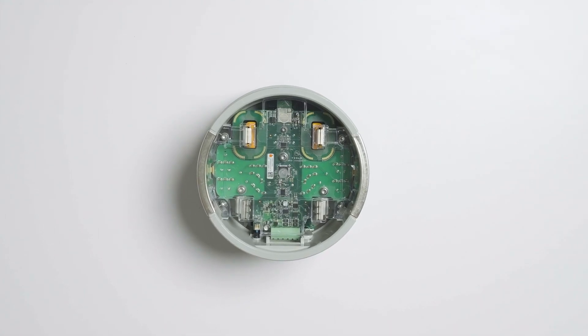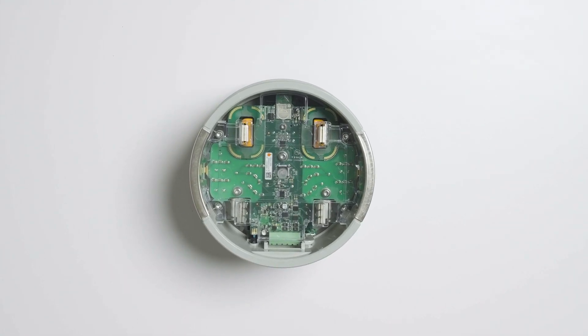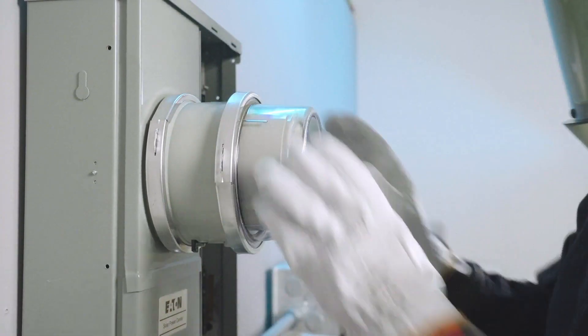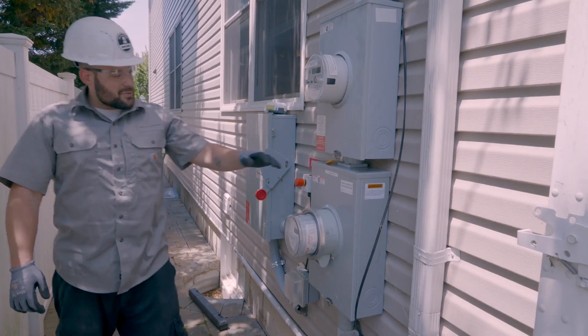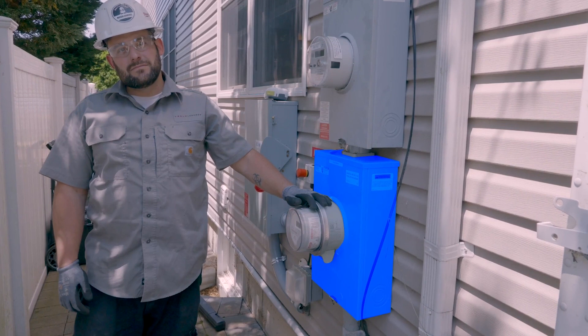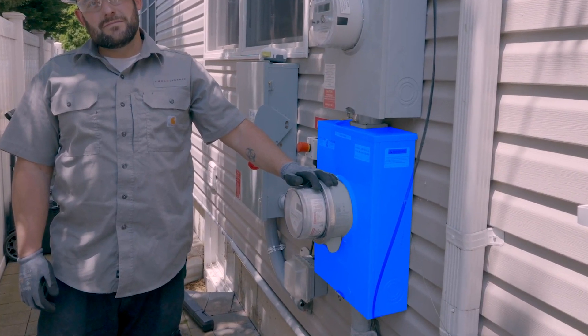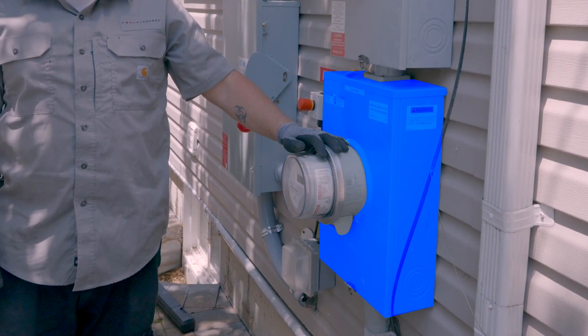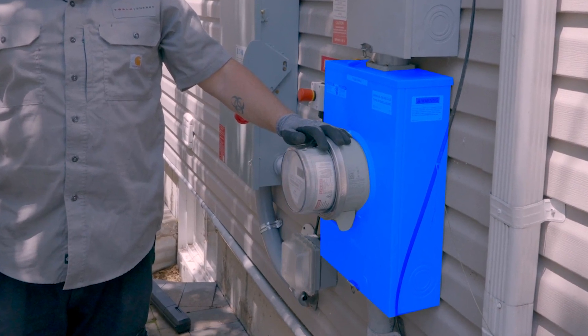Tesla Backup Switch is designed to be installed directly behind the customer's utility meter, disconnecting the home from the utility grid during a power outage. If the utility provider does not allow equipment behind the meter, or if the existing meter enclosure is incompatible, Backup Switch can be installed in a standalone meter panel that is downstream of the utility meter.